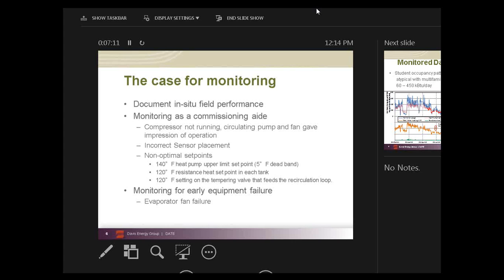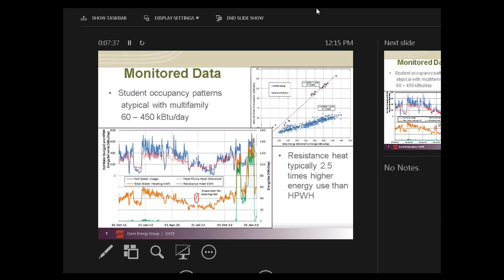And finally, near the end of monitoring, the controller lost its set points, and the unit again defaulted to electric resistance heat. And so we were still monitoring and were able to report that error rather quickly. There are 45 units in this housing complex, and the findings of this monitoring were shared with maintenance workers in hopes that the other units would be commissioned and operating the same.